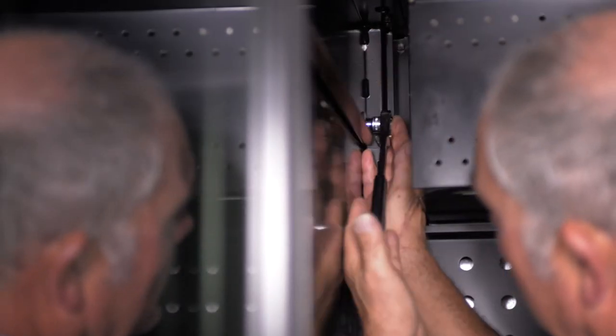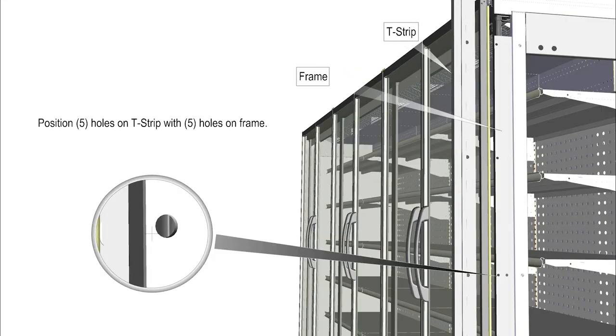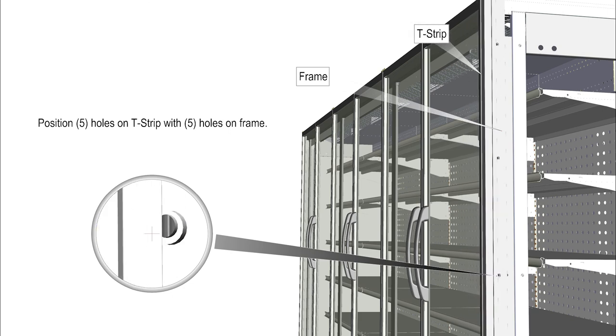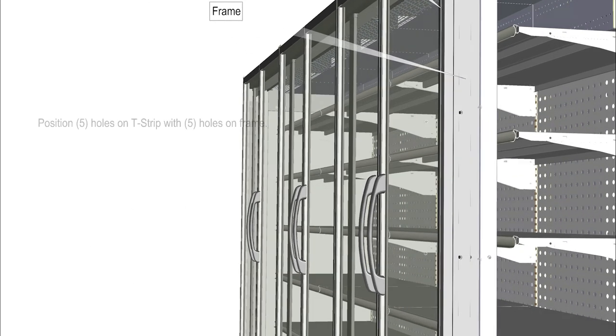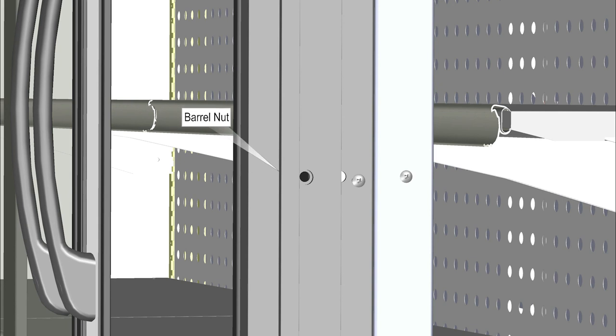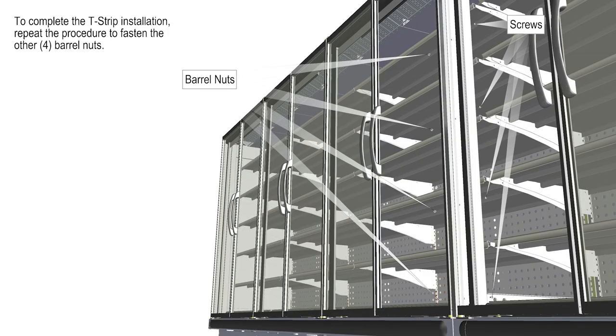The installer is using an impact gun for three of the four connections, but the rear upper bolt will need to be tightened by hand. If this were a cooler to cooler Crystal merchandiser lineup, the installer would bring the seams of the two cases together, loosely install the case bolts, then insert the center extrusion before tightening the bolts. He would then install the five barrel nuts and screws that secure the center extrusion.